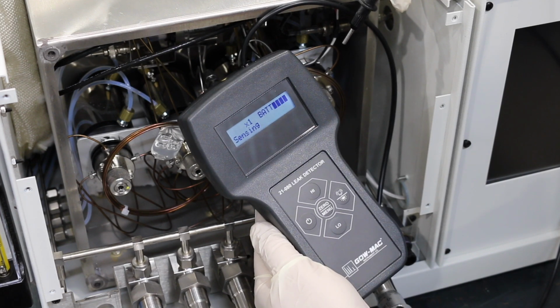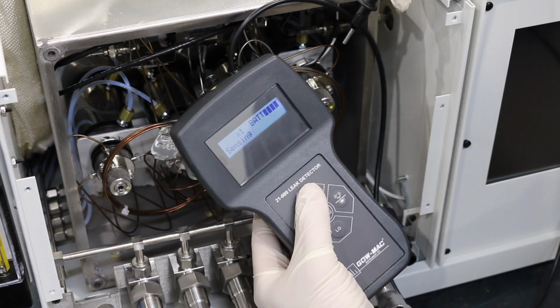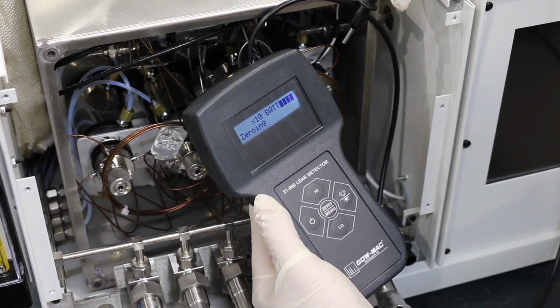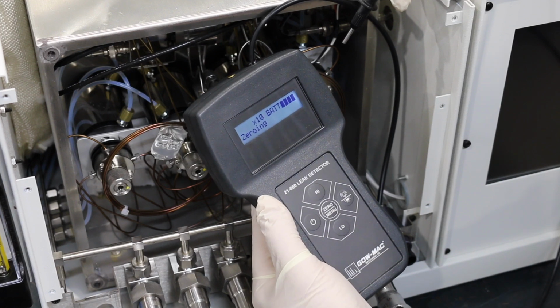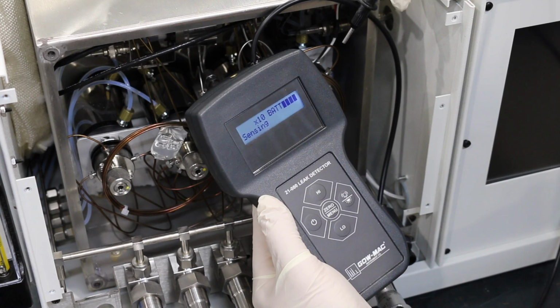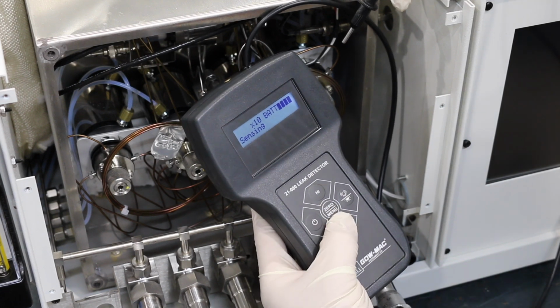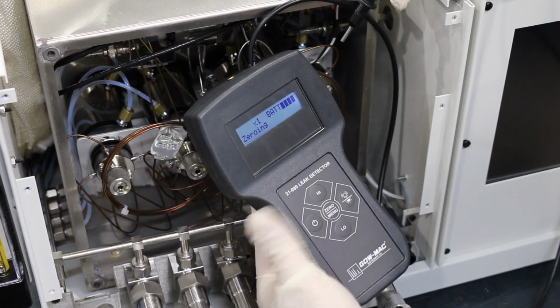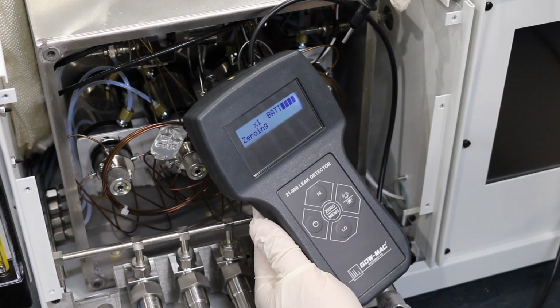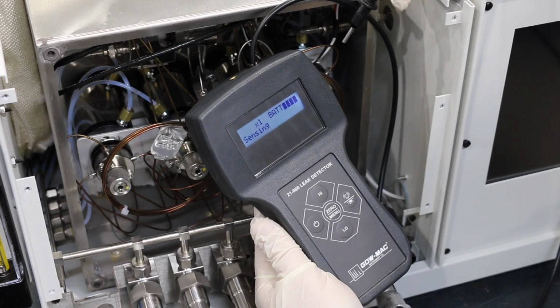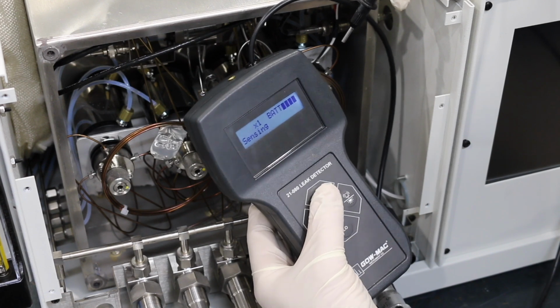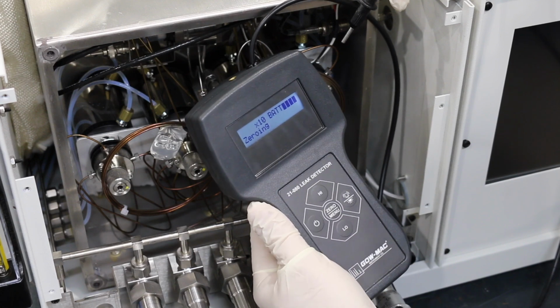2. Select low or high sensitivity. The high button increases sensitivity or gain by a factor of 10. The low button decreases the sensitivity or gain by a factor of 10. 3. After range is set, zeroing will appear on the screen. This also appears after the menu is closed or the menu zero button is pressed. The zeroing process adjusts the signal zero point to match the reference gas signal.